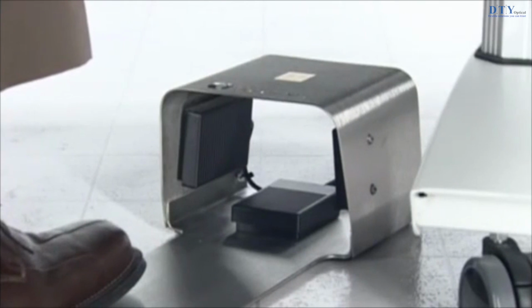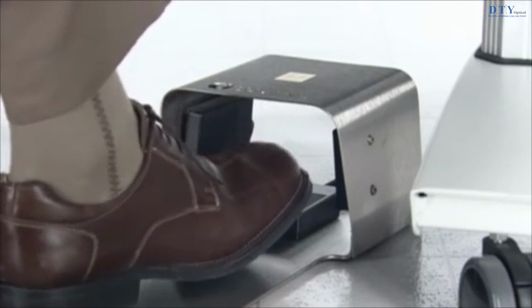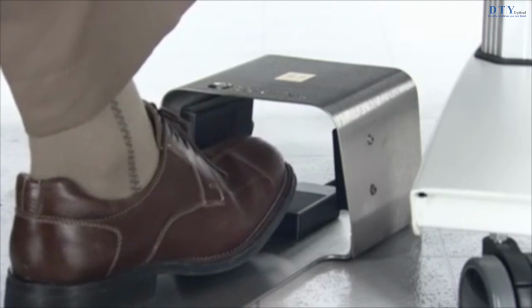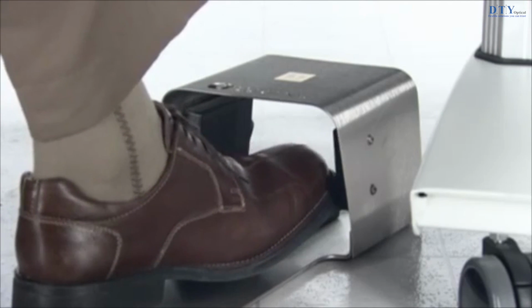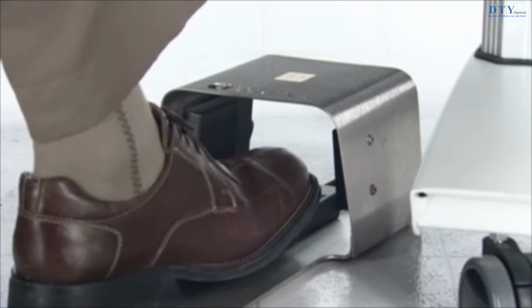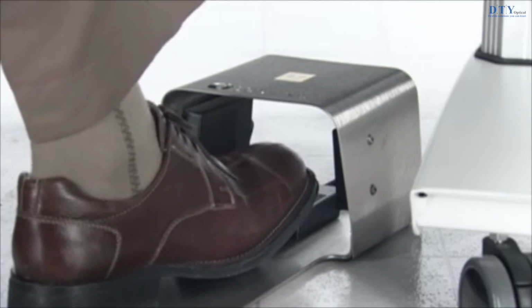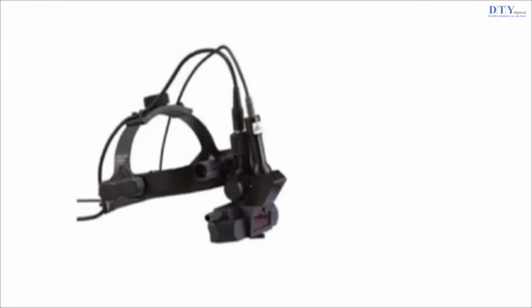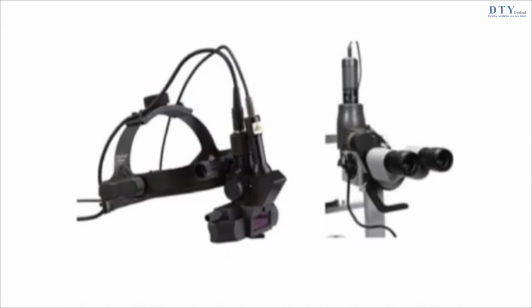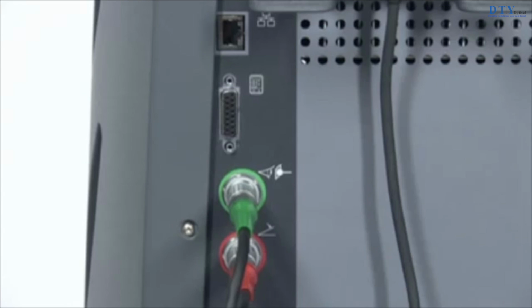If you are using the Power Ease foot switch, you can adjust the laser power by pressing the switches on the inside left, decreasing power, and right, increasing power, of the foot switch housing. A variety of fiber optic delivery devices with associated eye safety filters are available for use with Lumenis Vision One ophthalmic systems. Refer to the appropriate delivery device operator manuals for specific operating instructions.